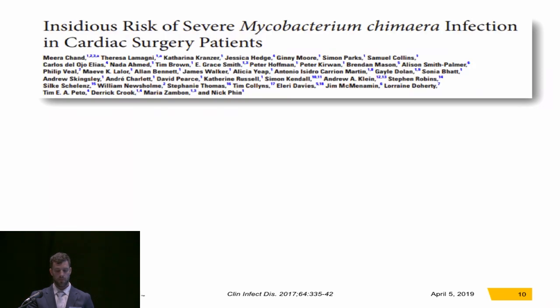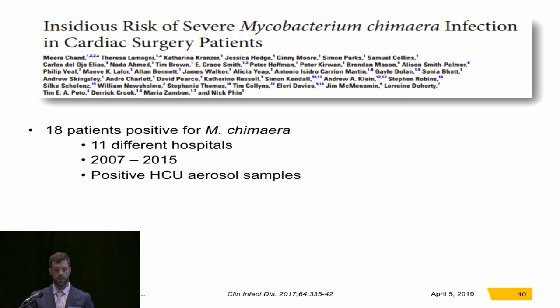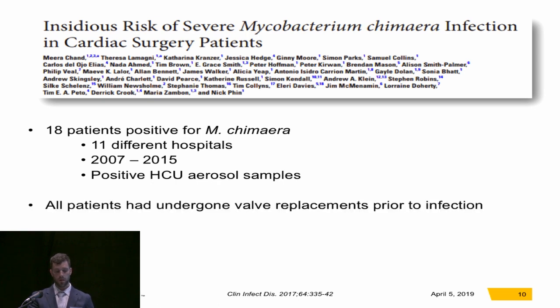Another study by a group in the UK in 2016 represents one of the larger patient populations. They had 18 patients who tested positive for M. chimaera over an eight-year period at 11 different hospitals. They all had positive heater cooler aerosol samples. All the patients had undergone valve replacements prior to the infection, the median time from surgery to presentation was 19 months, and half of these patients died.